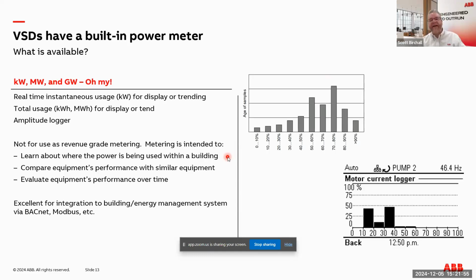And then on top of that is comparing like equipment. So if I got two air handlers that are same size that feed very similar areas, but I see one air handler has the drive drawing 20% more power than the other air handler, I want to go investigate, why is this air handler drawing 20% more power? Is there a problem with the filters and they never got changed out like they're supposed to? Is there something going wrong with the sensor? Are my duct static pressure set points different between the two and I didn't realize it? What is going on different between these? So it allows you to compare like equipment to each other.